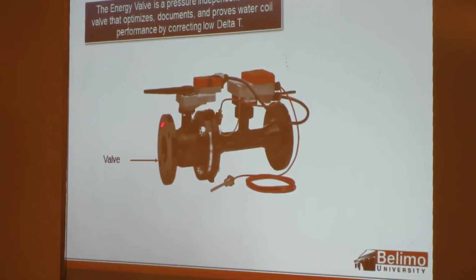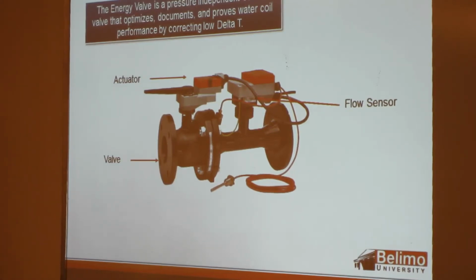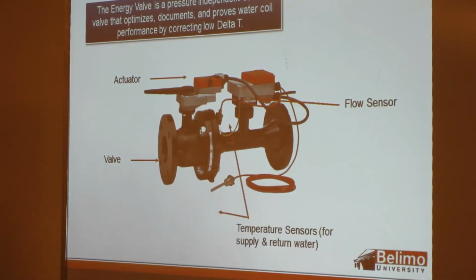So here we have the valve. Right on this side, that's basically just one of our flanged CCVs. Typical MFT actuator. Flow sensor, as we saw on the EPIV just a minute ago. Now the additions to this product: we have 2 temperature sensors, one embedded in the valve itself, the second to be mounted on the opposite side of the coil from the valve. By doing that, we're able to read the delta T across the valve. And then the last thing that was added was a BACnet application-specific controller.